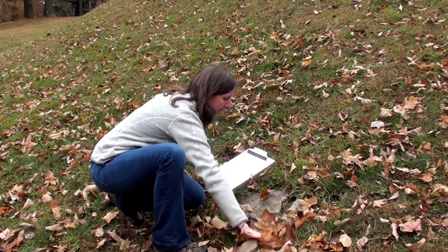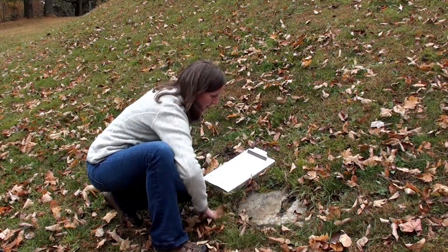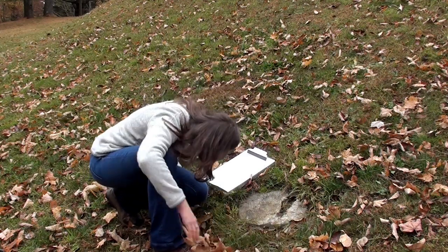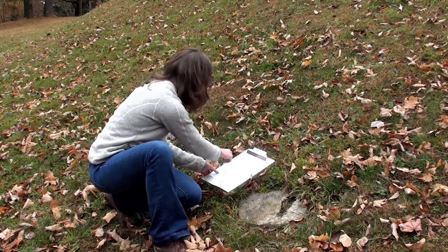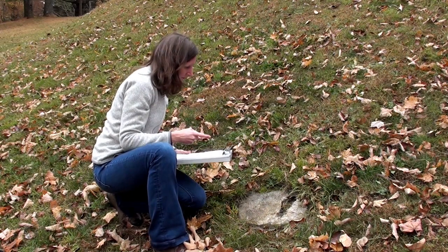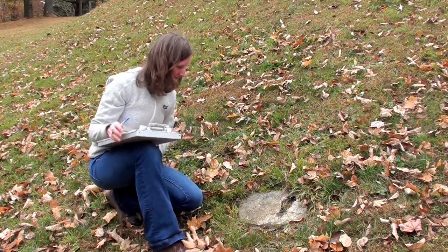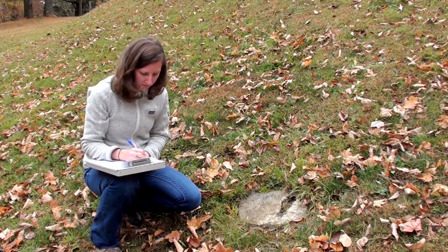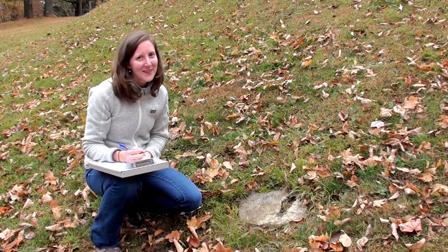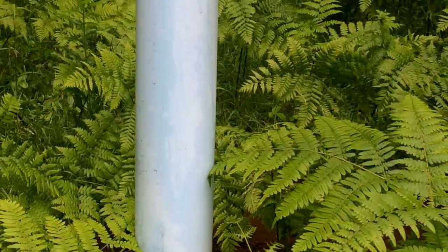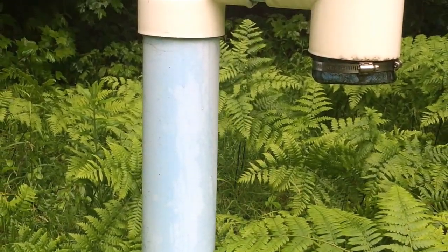In the storage tank example shown, the storage tank overflow is not properly constructed. It does not have a screen, it shows signs of buildup at the end of the pipe, and it does not terminate 12 to 24 inches above the surrounding area. When looking at storage tank vents, make sure that the vents are downturned or have some other means of preventing rainwater from entering the tank.